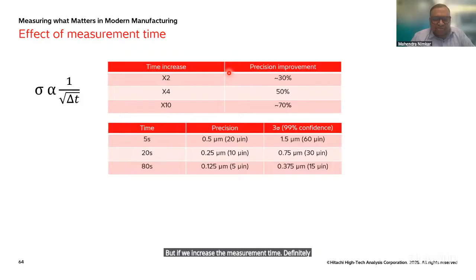This is something I want to mention about the effect of measurement time. Generally, it is like exposure with a camera, for example. As you increase the measurement time, your precision level is definitely going to go up. People ask what the measurement time is, and generally we say 15 seconds, which is a standard. But if you increase the measurement time, you can definitely increase the precision levels.